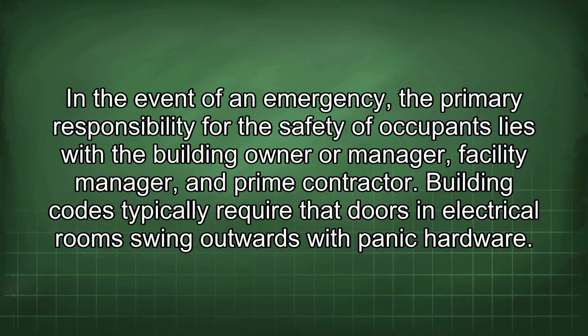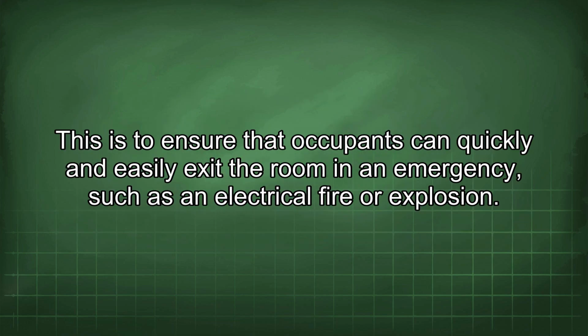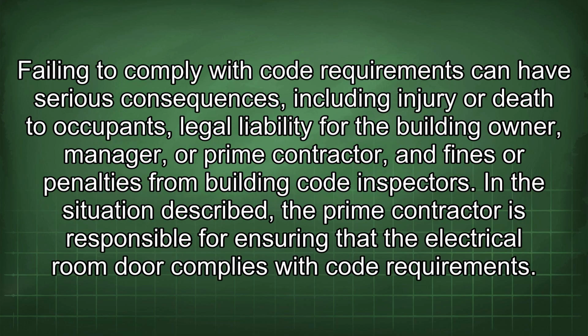In the event of an emergency, the primary responsibility for the safety of occupants lies with the building owner or manager, facility manager, and prime contractor. Building codes typically require that doors in electrical rooms swing outwards with panic hardware. This is to ensure that occupants can quickly and easily exit the room in an emergency, such as an electrical fire or explosion. Failing to comply with code requirements can have serious consequences, including injury or death to occupants, legal liability for the building owner, manager, or prime contractor, and fines or penalties from building code inspectors.